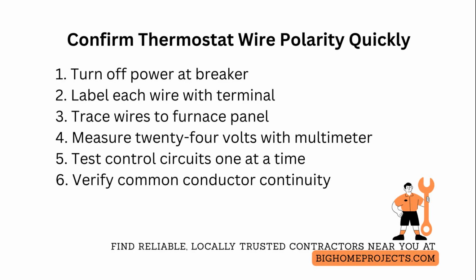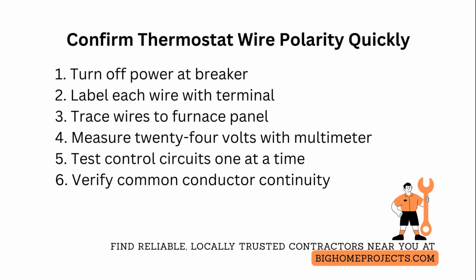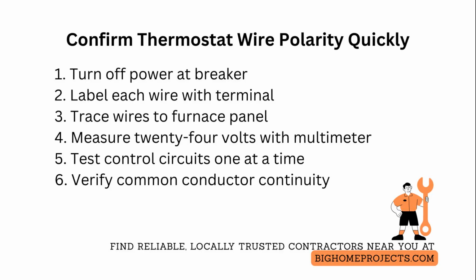For systems with heat pump or zone controls, test each control circuit one at a time. Apply the appropriate control signal at the board and verify the expected response: compressor contactor pulls in. Reversing valve energizes. Zone valve opens.